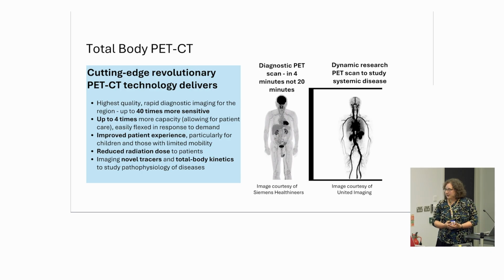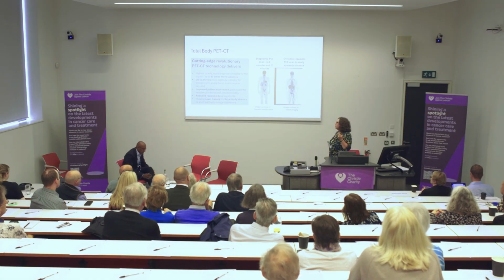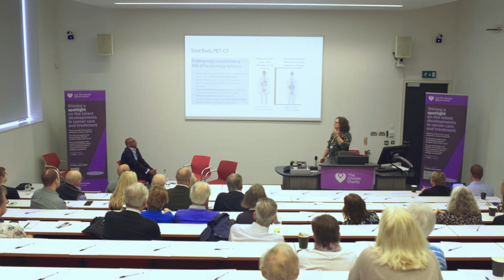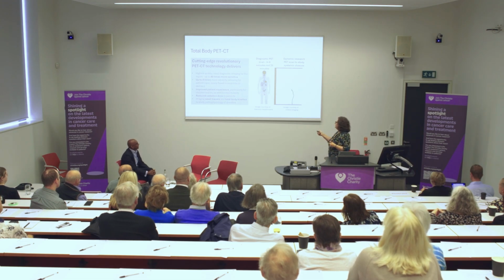That shorter scanning time is an improved patient experience. And also because a scanner is more sensitive, we don't have to give as much of the radioactive injection to them. So that in turn reduces the radiation dose to them and the associated risk. And because we can cover the patient in PET detector essentially, we can look at the injection as it goes into the body. And this is what this really lovely movie in the right hand panel shows. This is a super fast routine clinical scan. It's just one point in time. This is lots and lots of PET scans, probably over the course of an hour or so, which shows the delivery of that tracer. And as a research tool, looking at how those drugs distribute within the body, that's incredibly powerful. And it's not data that you can get when you're scanning this bit and then this bit and then this bit and then this bit to build up an image like that over 20 minutes.